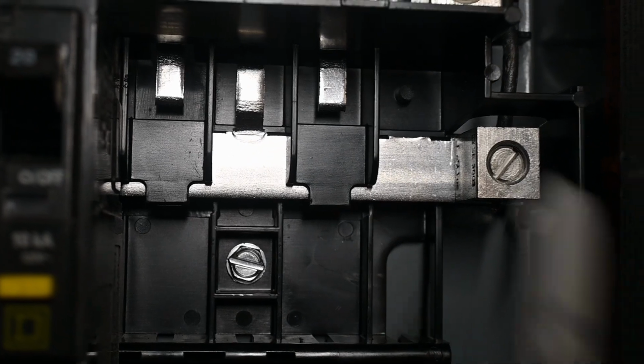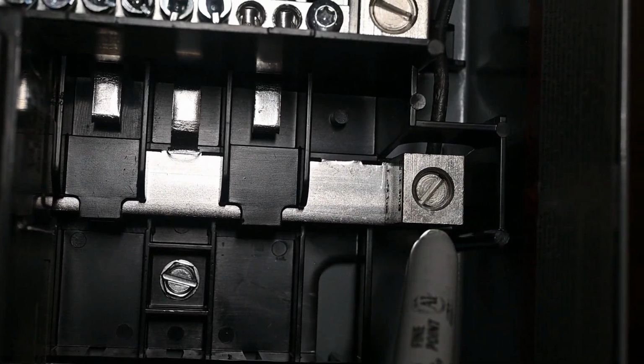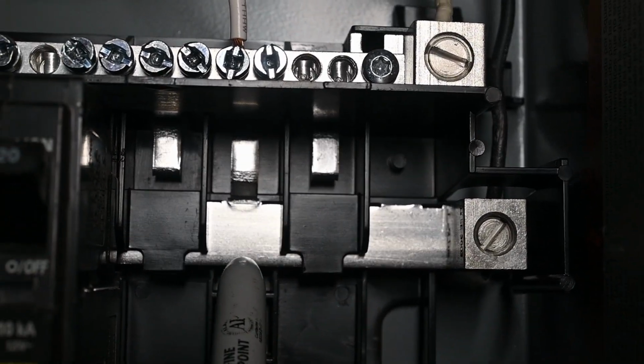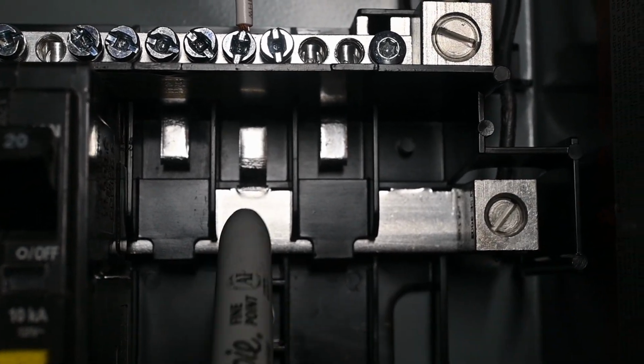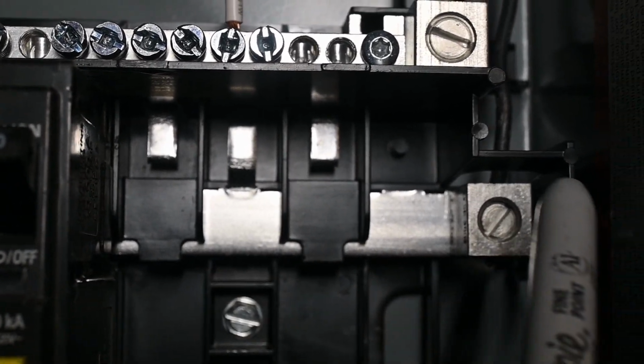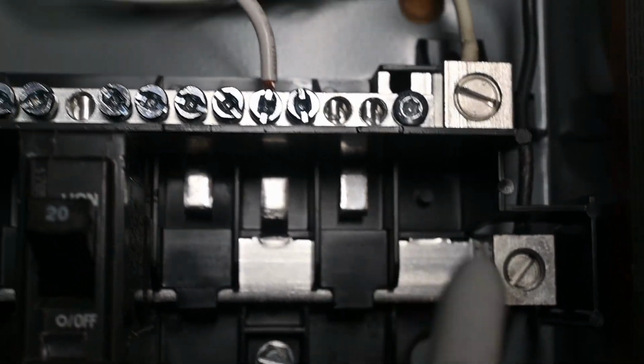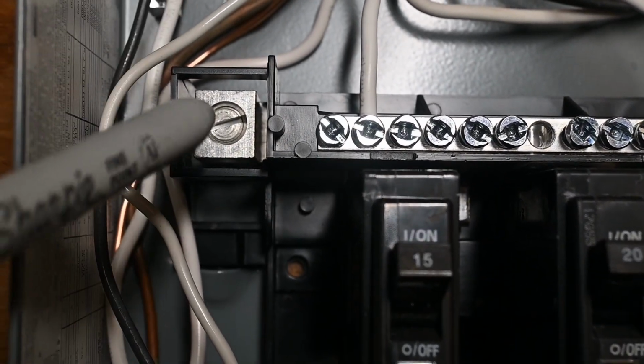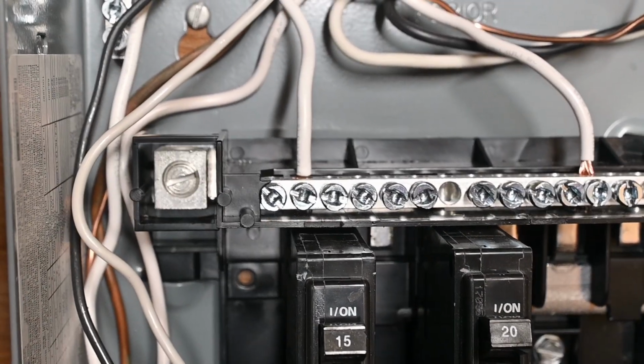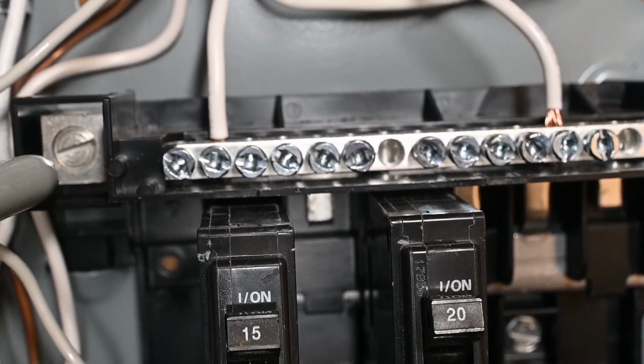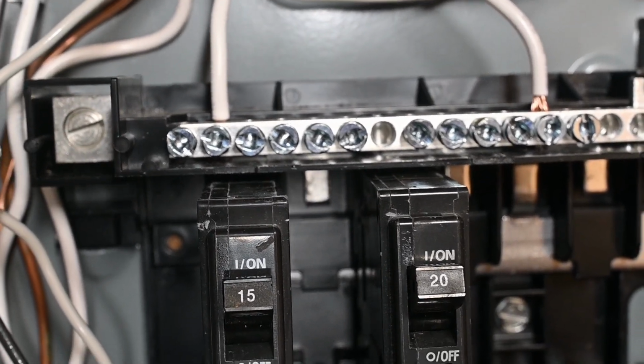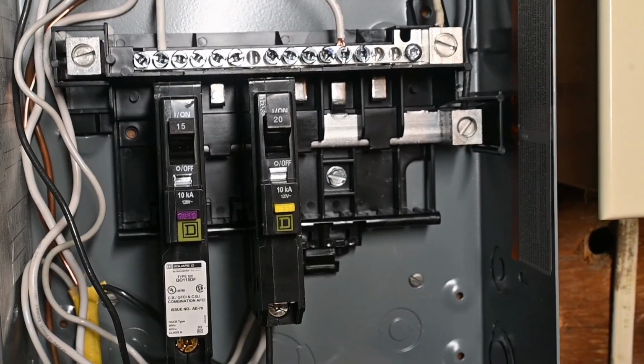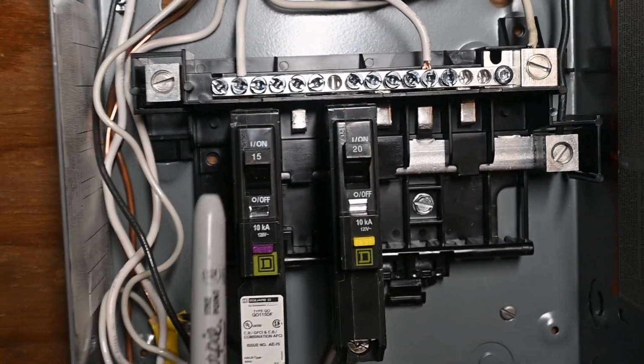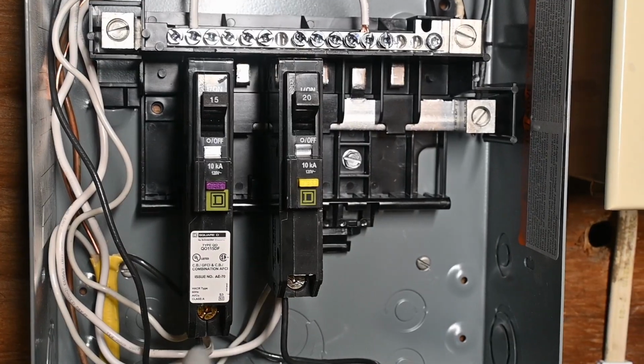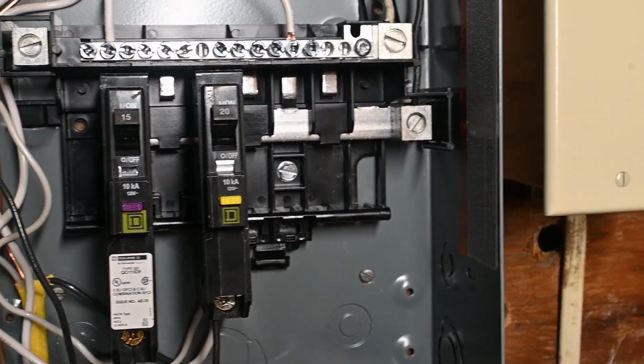And you can see back in here that by that being connected, that actually makes a connection to every other space inside of this panel. So you can see this space right there is connected to this leg. That space right there is connected to the leg that leads over to this terminal over here, and so on and so forth. It's just that we don't have a second leg of 120 volts coming into this panel. So since every other slot is dead in this particular panel, we would technically only have room for 3 circuits. And we've got 2 already in use, so we have 1 more that's available.